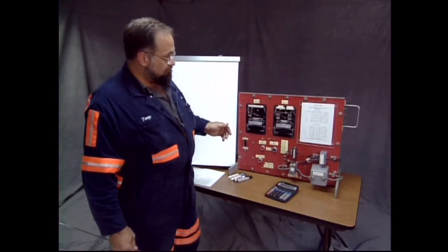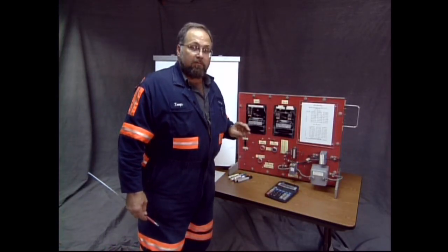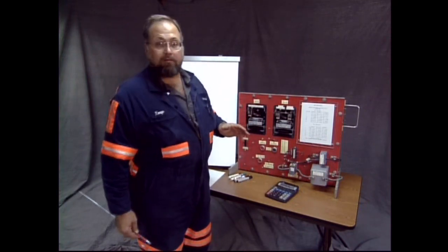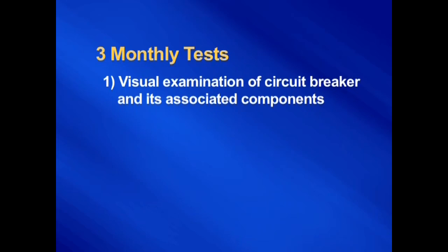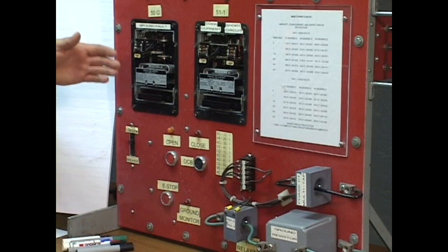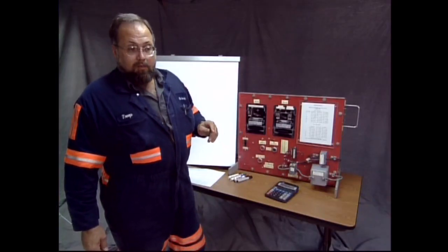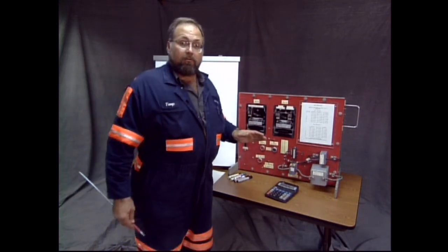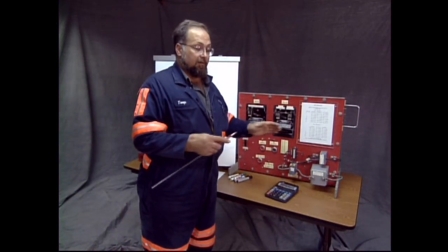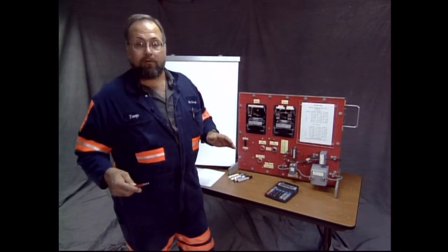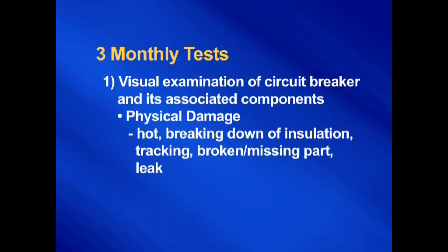Those 5. Now, you have to do 3 things for your monthly examination at the mine site. And those 3 things are: you have to make a visual examination of the circuit breaker and its associated componentry, its auxiliary devices. Now, these are the auxiliary devices. You have a visual examination. That's 1. To complete a visual, you need to look at the circuit breaker. Sometimes they're not readily in sight. You might have to take a cover off to view the circuit breaker. And what you're looking for is obvious physical damage. You've got something hot, evidence of something being hot. You've got a breaking down of the insulation, a tracking. You've got a broken part, a missing part, a leak.